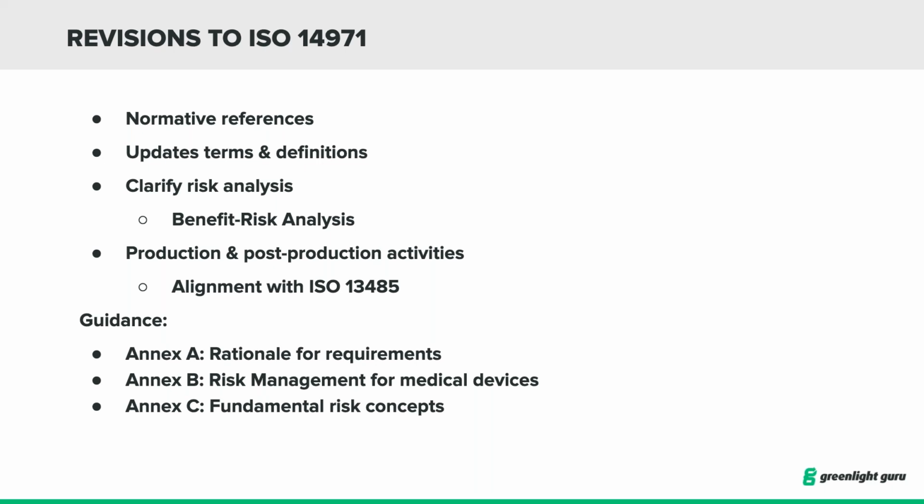One of the, I don't want to say big ones, but it's kind of a label change. Instead of calling it a risk benefit analysis, it's now being referred to as benefit risk analysis. I guess that's good, put the benefit in front of the risk. But there are some additional guidances that are defined within that standard as well.